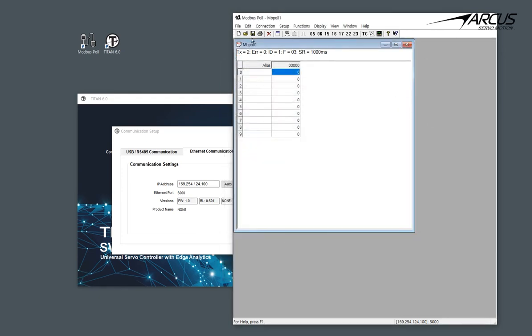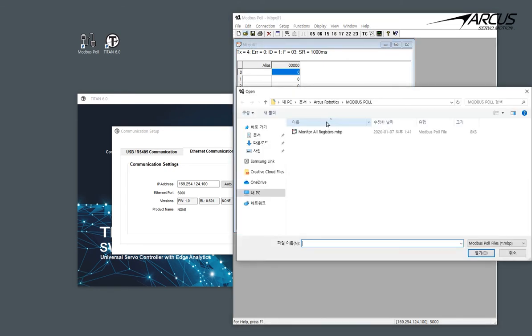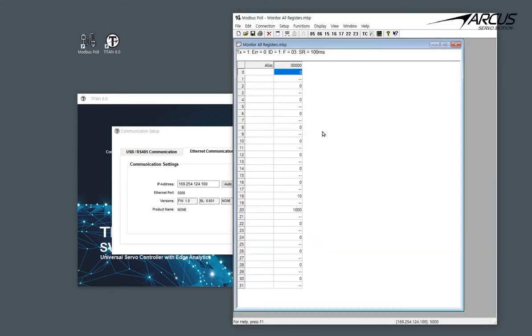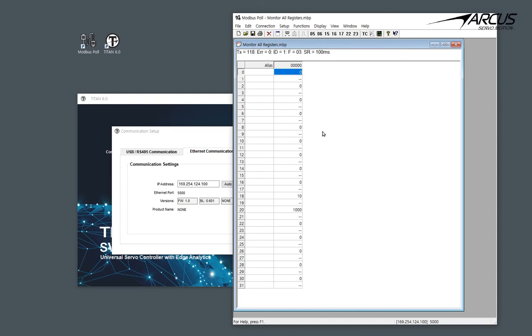Let's open up the setup file that we created before that monitors all the registers using the function 3. There are a total of 32 registers of 16-bit data. Since we are using the 32-bit signed Big Endian, we will set the format as 32-bit register Big Endian and read the total of 16 32-bit registers.